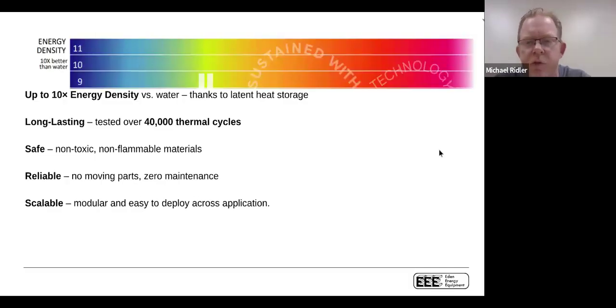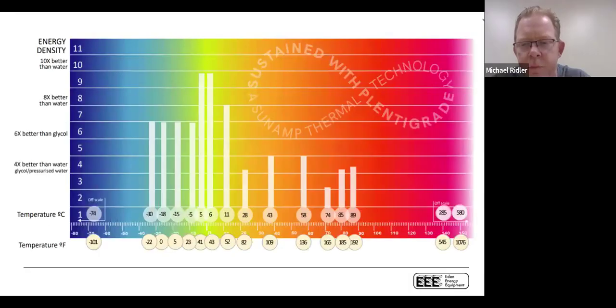As we walk through what it looks like, and remember earlier where I said it's 3.5 to 10 times smaller, this is where it's really important. What you're seeing here is phase change batteries that operate at different temperatures, everywhere from 5 degrees Celsius and lower, upwards of 89 degrees Celsius. The energy density varies anywhere from 3.5 to 10 times. The only thing I'm going to leave with you here is that you can actually buy phase change batteries that store BTUs for cooling, not just BTUs for heating. That's an important distinction to know.